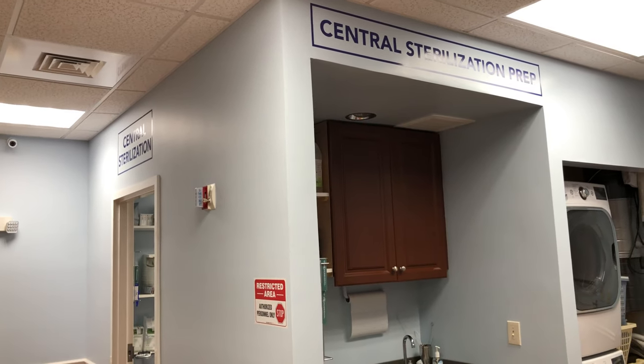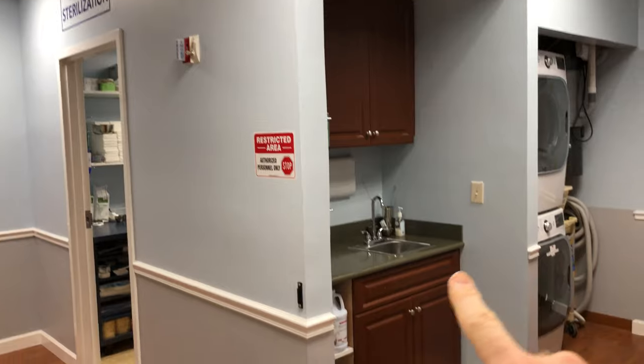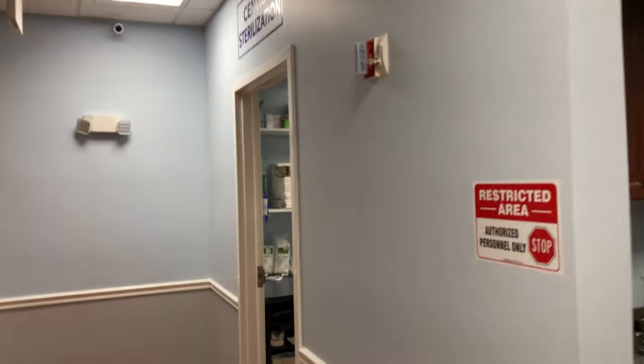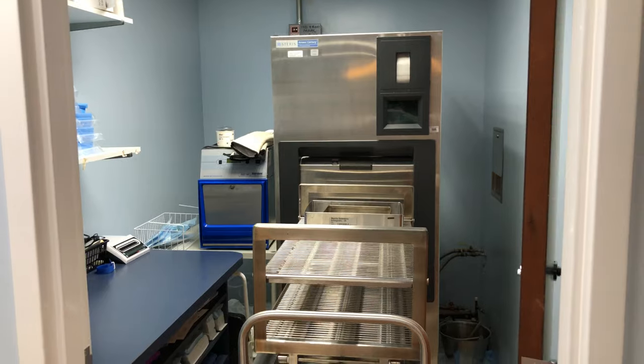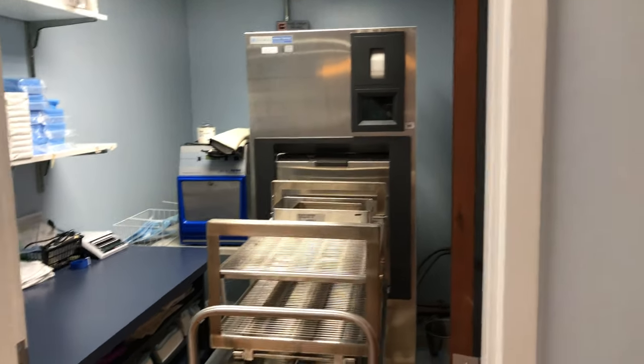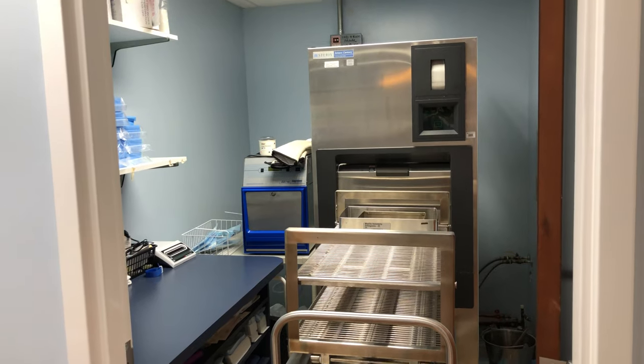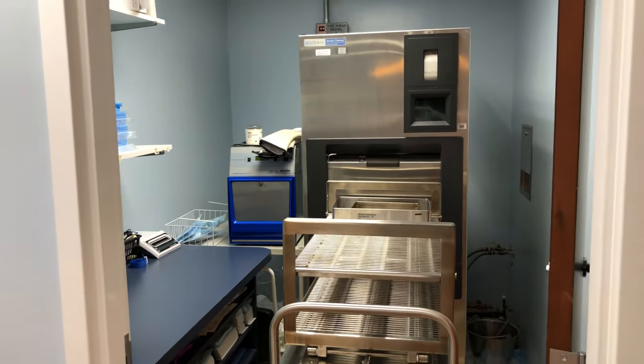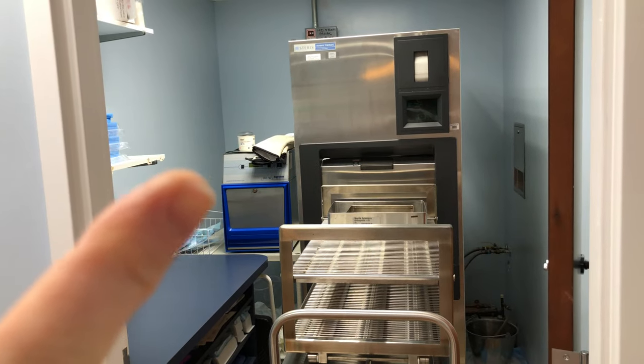We're going to go over here — this is our central sterilization prep area and then central sterilization room. When we have surgical instruments that need to be sterilized, they're cleaned here first and then they move into central sterilization. In here is the big beast — this is a ginormous order autoclave, a hospital-level grade-two autoclave. It uses heat, pressure, steam, and vacuum to sterilize our surgical instruments. Anything that can't take the high temperatures goes into this gas sterilization unit, which is much safer for items with plastic on them.